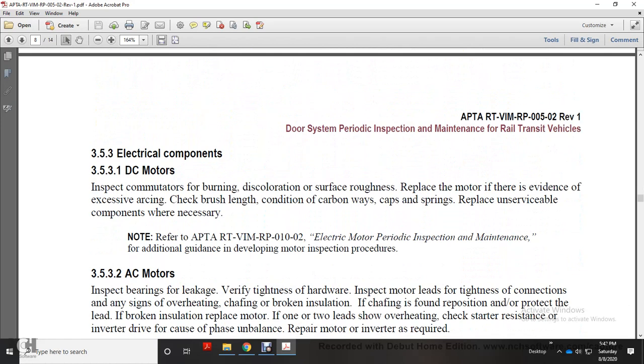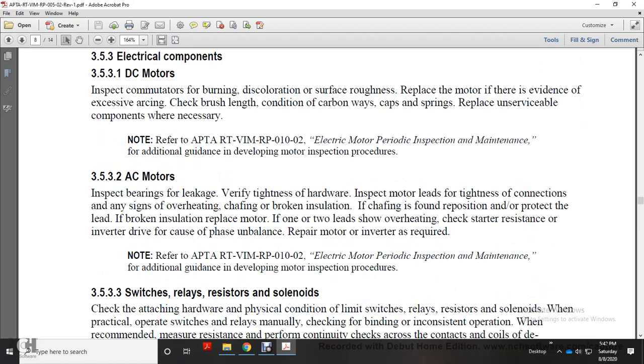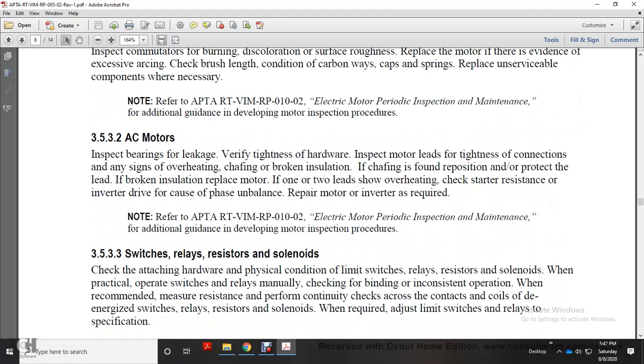Alright, 353, electrical components of the DC motor. Inspect the commutator for burning, discoloration, surface roughness, replace the motor, evidence of excess arcing, check brush length, length and condition of the carbon brush, the caps, and springs in place. Replace unserviceable components where necessary. Note: refer to the APTA RT VIM RP 01002 electrical motor periodic inspection maintenance for additional guidance developing motor inspection procedures.